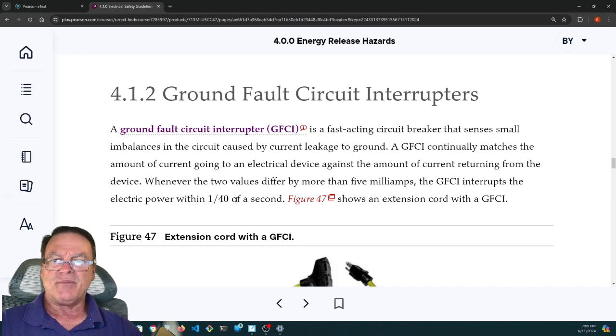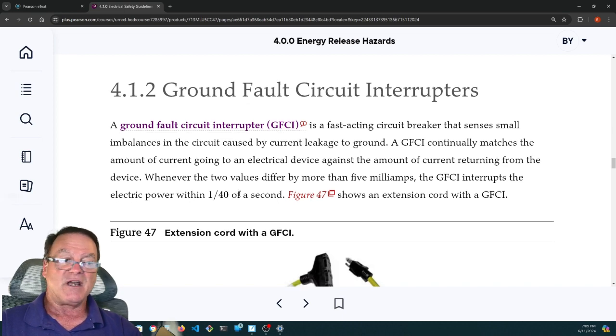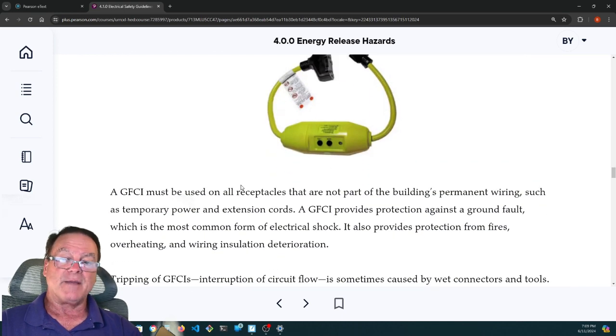So if you get between the hot and the neutral on the load side of a GFCI circuit breaker, it won't trip. You'll get hurt. If you go between hot and ground, then it'll trip. Because if there's a difference of even between 4 and 6 thousandths of an amp, 4 to 6 milliamps, it will trip that GFCI. They say 5 milliamps plus or minus 1 milliamp.